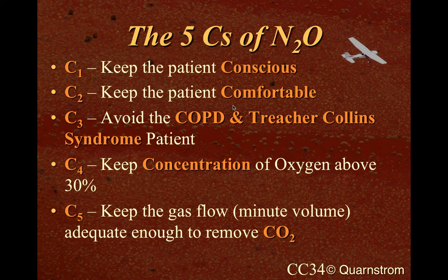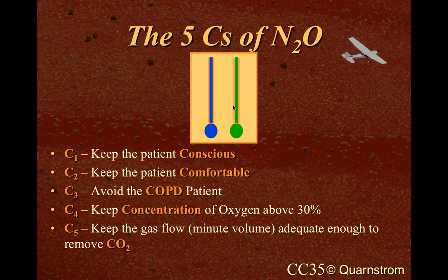And the 5th C, keep the gas flow, the minute volume, adequate to remove the patient's carbon dioxide, meaning you got to be giving them, rough rule of thumb, at least 5 liters per minute of fresh gas.